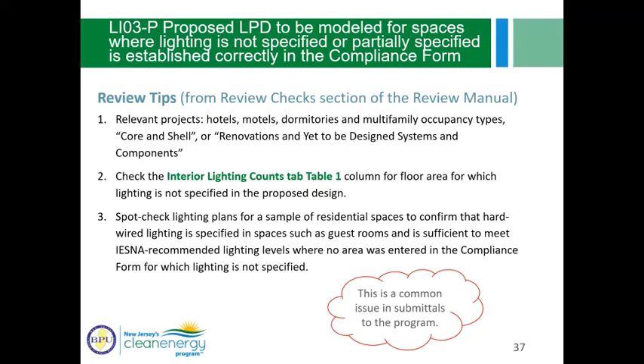This check is especially relevant to hotels, motels, multifamily, and core and shell projects, where either lighting is not yet designed, like core and shell, or where there are areas where the design intent is for these spaces to be supplemented with plug-in fixtures. It's very common, especially in multifamily, for the designers to design hardwired fixtures for the bathrooms, the kitchens, and maybe they put one in the hallway. And then the assumption is that plug-in fixtures will be used by the occupants to provide the remainder of the needed lighting.